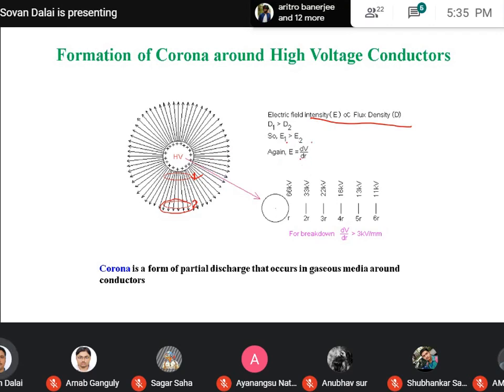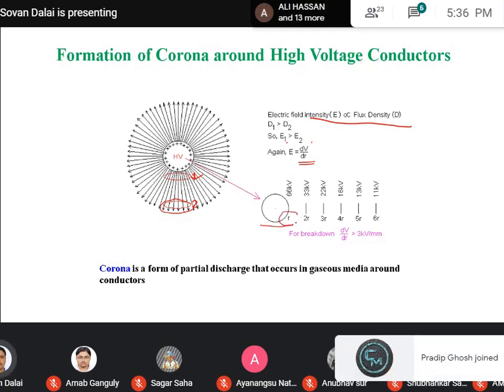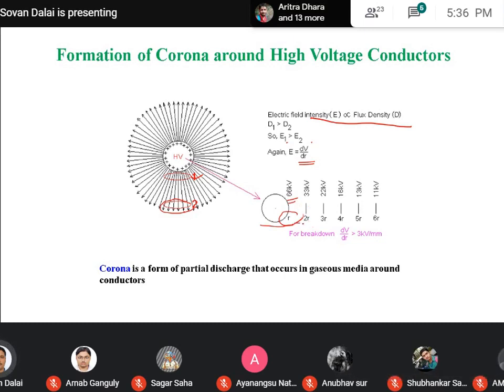So we can represent the electric field intensity in terms of dV by dr. This is the representation at the surface of the conductor, with the electric field at 66 kV, and gradually, as you travel far away from it, the voltage level reduces. When breakdown occurs, when dV by dr is greater than 3 kV per millimeter, corona starts. So corona is a form of partial discharge that occurs in the gaseous medium around the conductor.